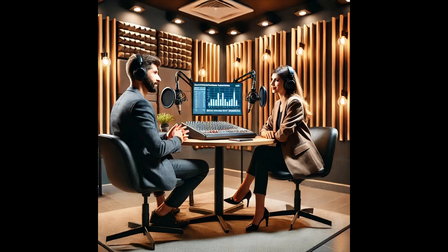And finally, retention. How long do these records need to hang around? Good question. It's the longer of 2 periods, either the expected life of the device itself or at least 2 years from the date the device was released for commercial distribution. Okay, so potentially quite a long time for some devices. Definitely. Ensures records are there if issues arise down the road. That gives us a really solid grounding in the FDA's world.